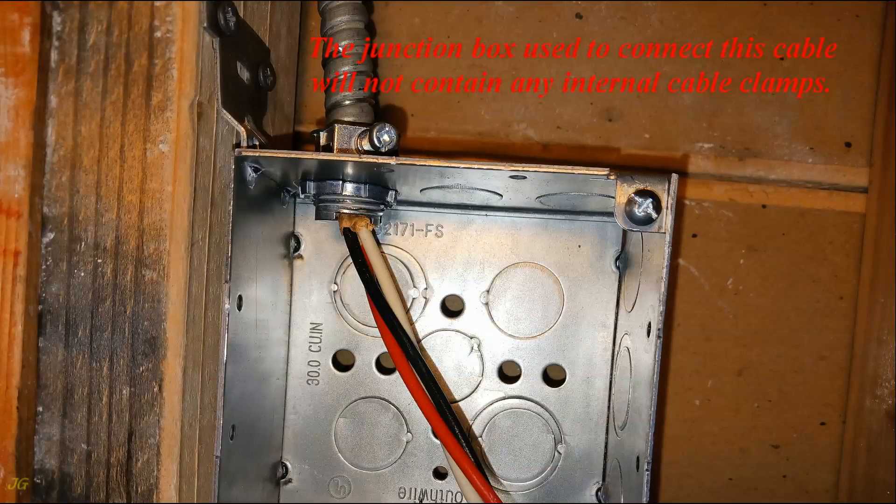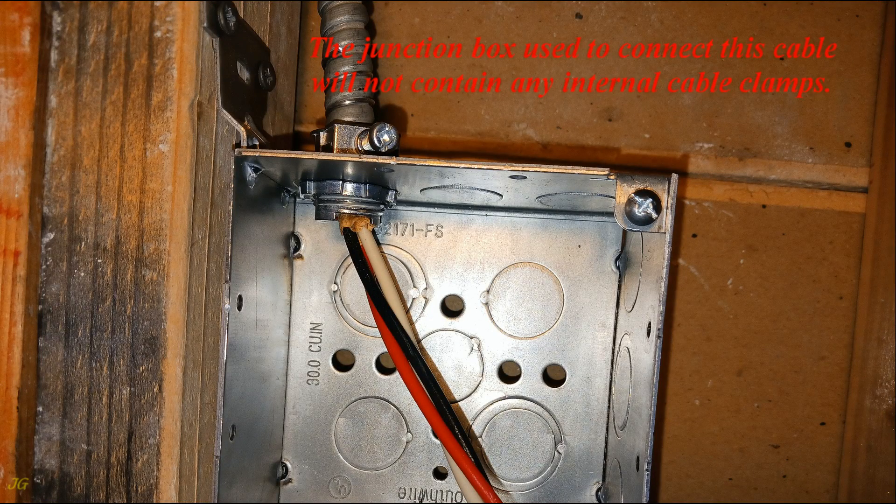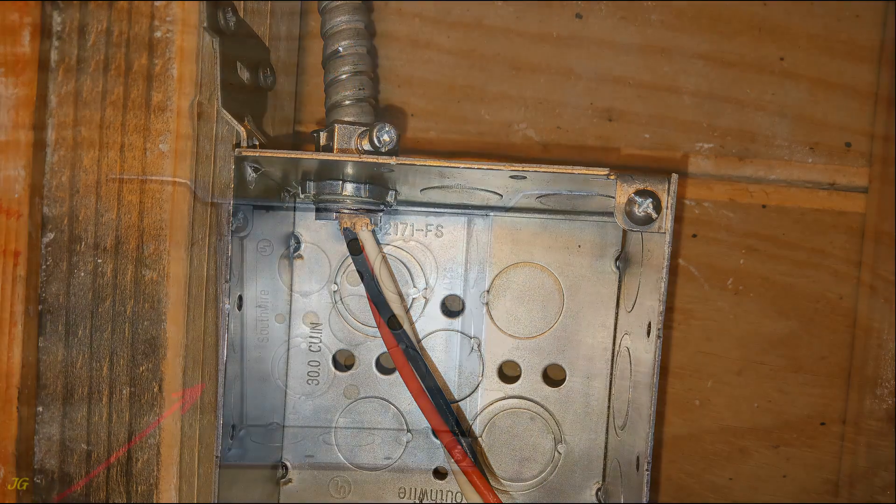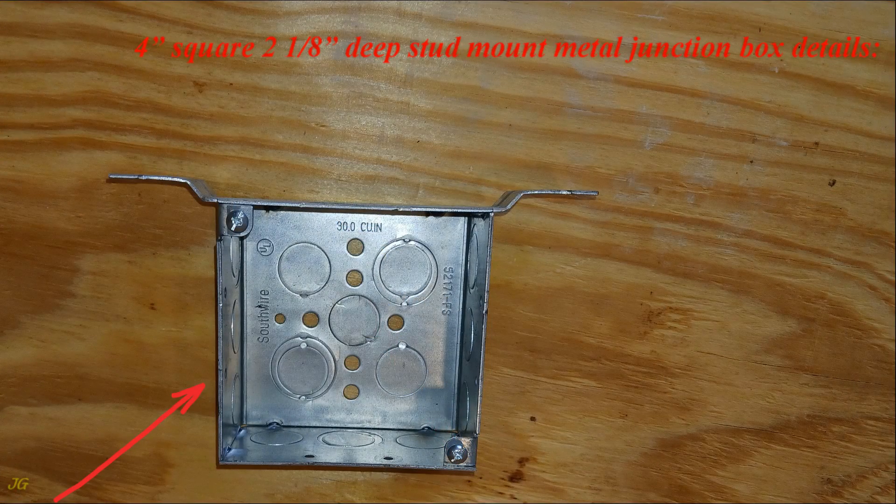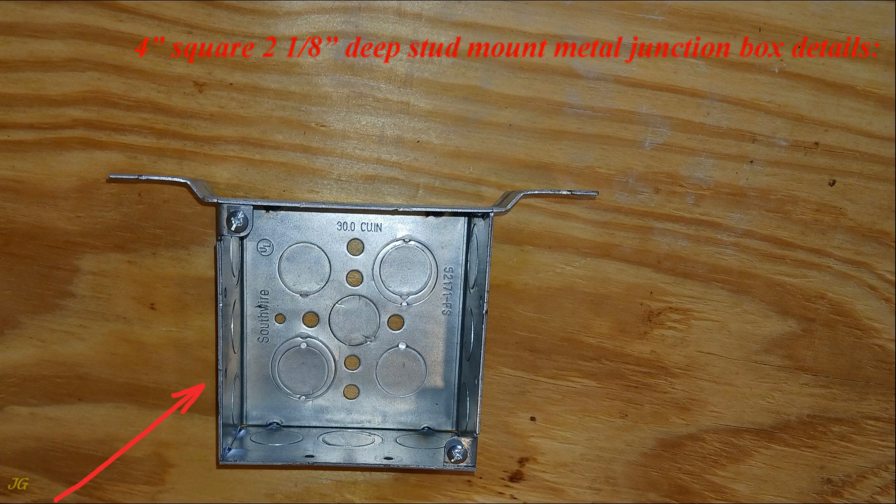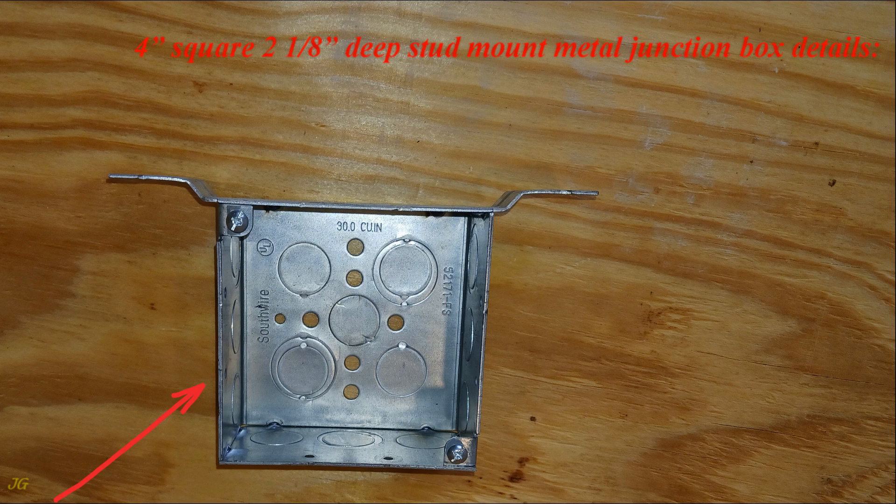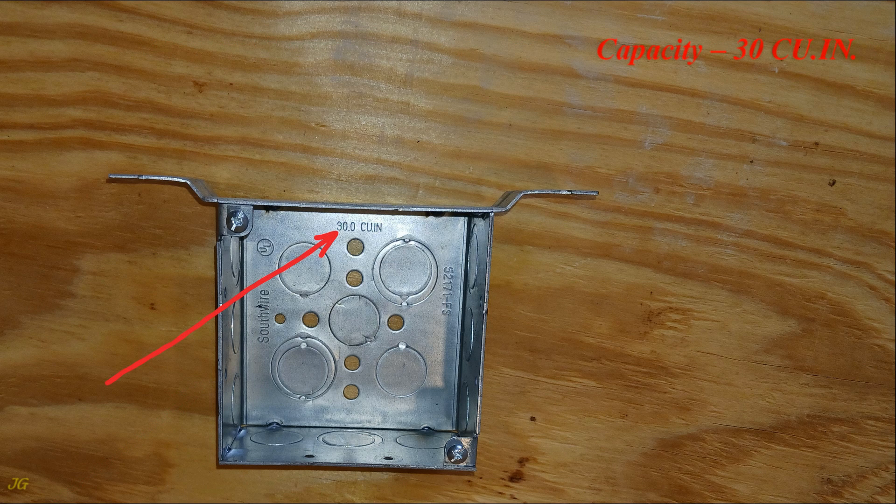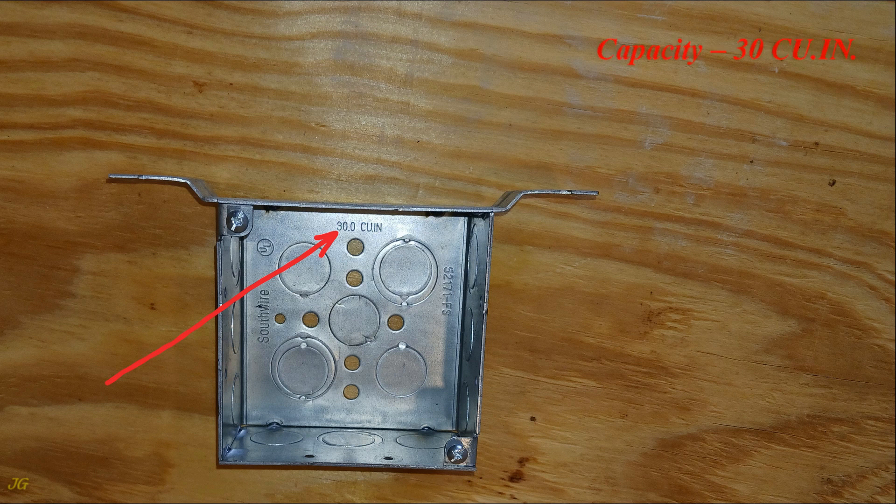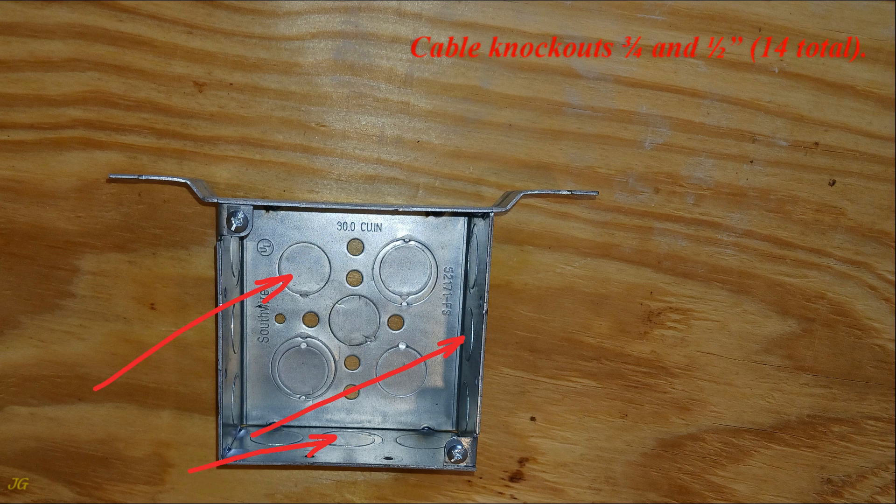The junction box used to connect this cable will not contain any internal cable clamps. 4-inch square 2 and 1/8-inch deep stud mount metal junction box details. Capacity 30 cubic inches. Cable knockouts 3/4 and 1/2 inch, 14 total.